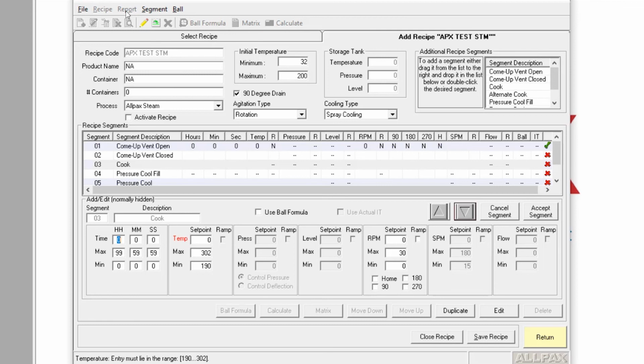It's trying to add air to compensate for that rapid collapse of steam, and it's begun sprinkling the water on. So you'll see a little bit of movement in your pressure level right there, but the pump will pulse for a few seconds during that step. If you select the flood cool step, it's already filled up the entire tank with water. There's no need to pulse the pump. It will just run normally.